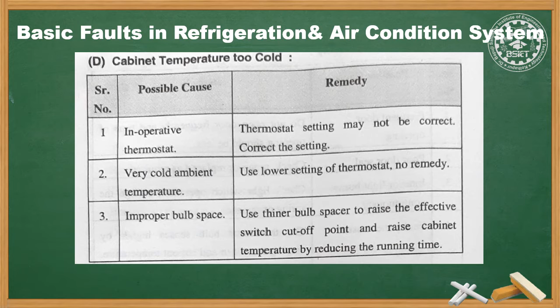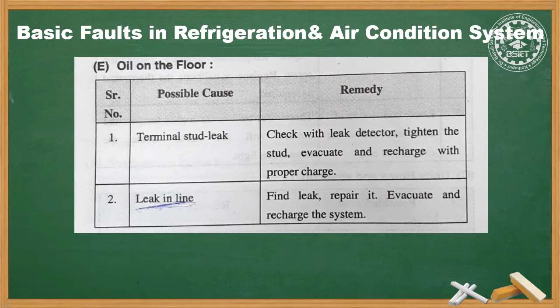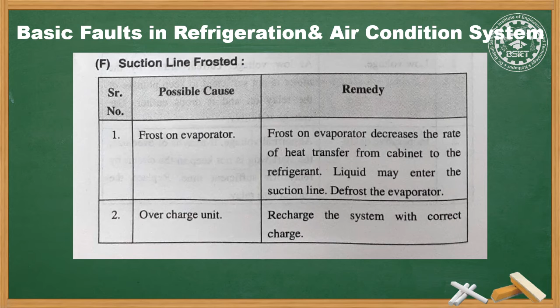The next is oil on the floor. Possible causes are either the terminal stud is leaking or there is a leak in the line. For this, find the leak, repair it and if possible, recharge it. Suction line frosted, that is, ice is formed over the suction line or over the evaporator. The possible cause is frost on the evaporator. The remedy is to defrost the evaporator and, if the unit is overcharged, recharge the system with the correct charge.